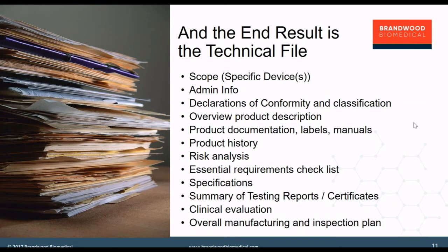It is not required for the technical file to include every single report which has been produced as part of the design and development process, but you should include sufficient information so the complete story is basically captured in the technical file as to how you are meeting the essential requirements there. So, compliance reports with the relevant consensus standards have to be included in there. And the primary verification as it relates to your system risk analysis also should be included in the technical file.